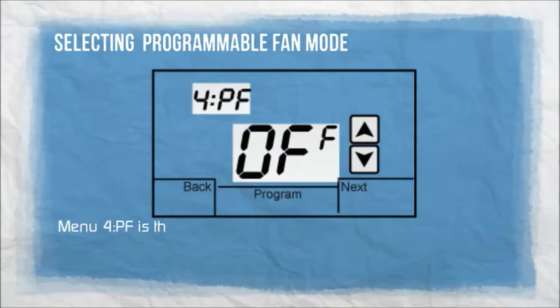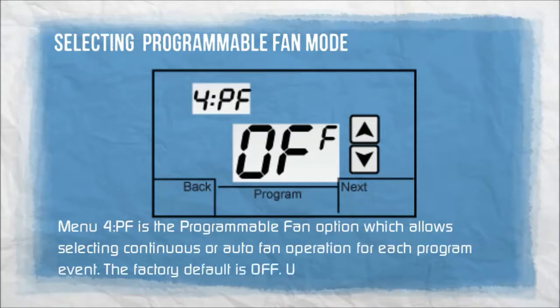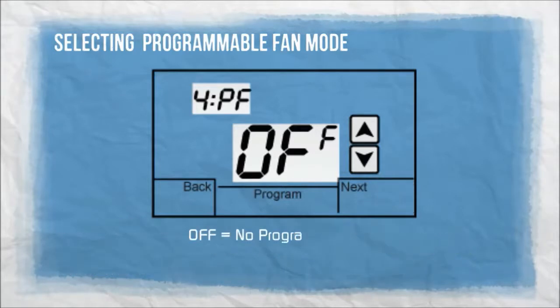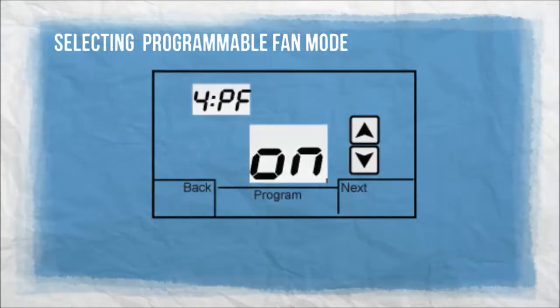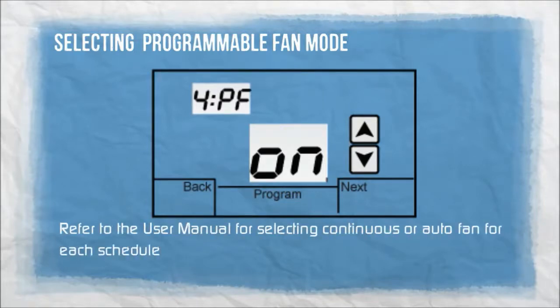Menu 4PF is the programmable fan option, which allows selecting continuous or auto-fan operation for each program event. The factory default is off. Use the up and down arrows to select a programmable fan option: off for no programmable fan, on for programmable fan operation. Refer to the user manual for selecting continuous or auto-fan for each scheduled event when the programmable fan option is on.